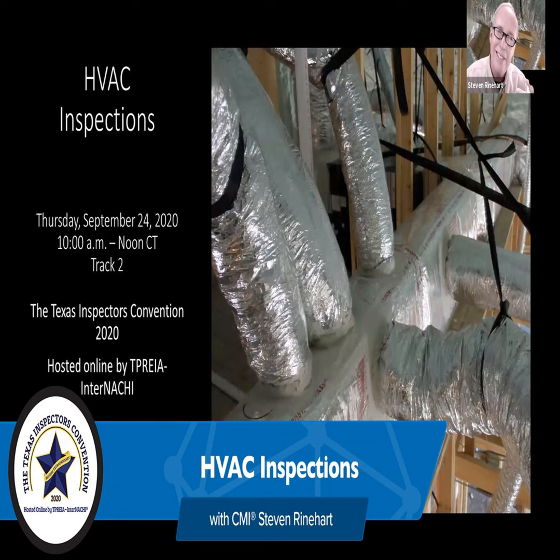Electronic air filters, I might make a note that it's there. Multi-stage, they're just sequencers. Those are what tell the unit how many of the heat strips to come on. Heat reclaimers, the only thing I know there is de-superheating, where you might see a heat pump that's connected into your water heater. It's using the heat from your compressor to heat your water heater. Only seen a few of them. Got one up the street where I live, but rare.